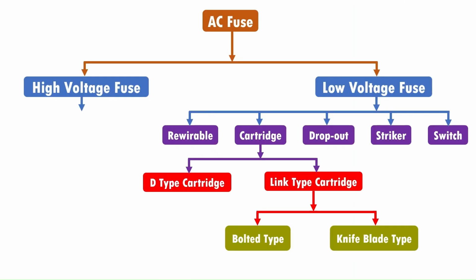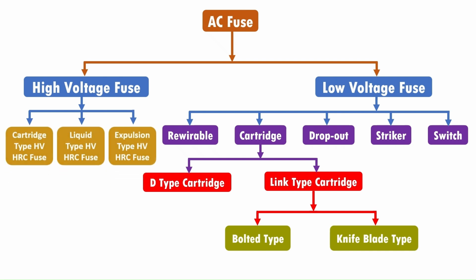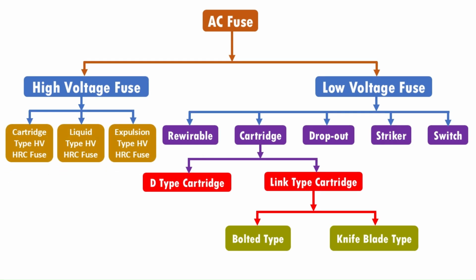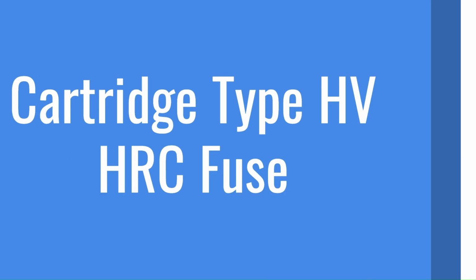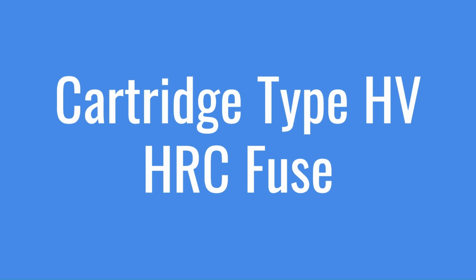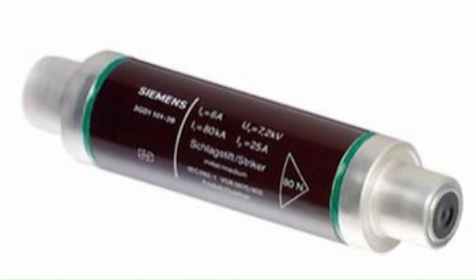High voltage HRC fuses are mainly classified into 3 types: cartridge type high voltage HRC fuse, liquid type high voltage HRC fuse, and expulsion type high voltage HRC fuse. In a cartridge type high voltage HRC fuse, the fuse element is wound in the shape of a helix, which avoids the corona effect at higher voltages. It has two fuse elements placed parallel with each other. One is of low resistance and the other is of high resistance. The low resistance wire carries the normal current, which is blown out and reduces the short circuit current during the fault condition.